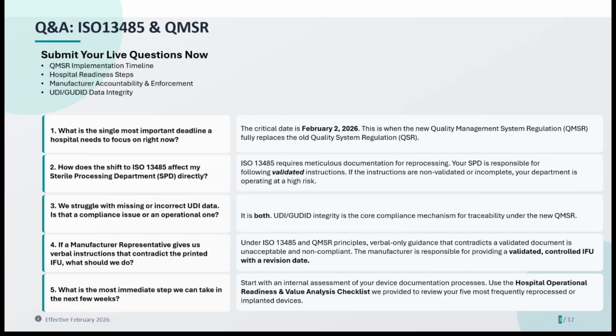Number two, how does the shift to ISO 13485 affect my sterile processing department directly? Well, ISO 13485 requires meticulous documentation for reprocessing. If an IFU is missing steps for cleaning, rinsing, inspection, sterilization, or drying, or is vague, or has contradictory instructions, the device is not compliant and puts your SPD at high risk. This alignment gives the SPD the leverage it needs to demand complete, validated IFUs from the manufacturer.